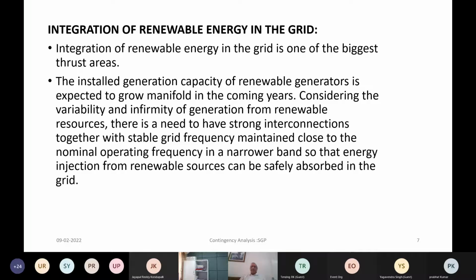Otherwise, with the present balancing mechanism of primary control, secondary control, and tertiary control, the time to respond, as we were discussing yesterday, is even for the primary response from 15 seconds to 15 minutes, then the secondary response, followed by the tertiary response, which is manual. That sort of response time to balance the generation with the given load condition will not do the required frequency control, and hence storage becomes necessary.